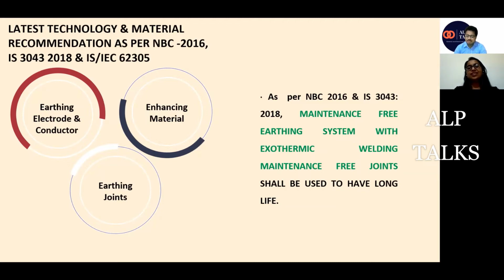It is just a chemical composition along with the metal, right? The maintenance-free means, exactly, it is this chemical compound only which is making the system maintenance free, protecting our earthing for a longer run, which is not corroding my earthing rod also, and it is maintaining the system for a longer lifespan. Generally these metals are normal iron, or GI, or any tin coating, or what is the generally recommended practice for that?